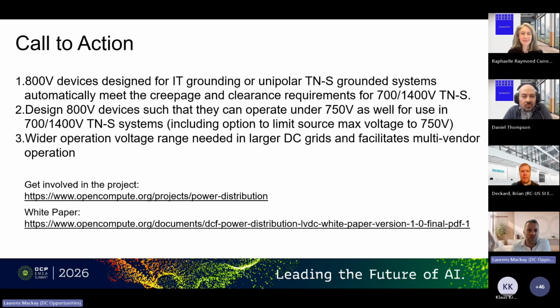That allows you to use the full 1500 volt range in your data center, which is the limit of low voltage, which surely we don't want to go above with the servers. The second point is, to allow that, you need to make sure you can operate underneath 750 volts as well, because you want to stay underneath that to stay under the 1500 volt range.